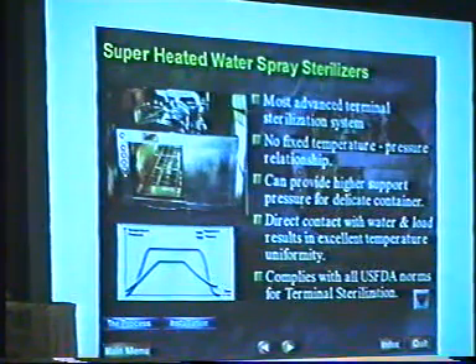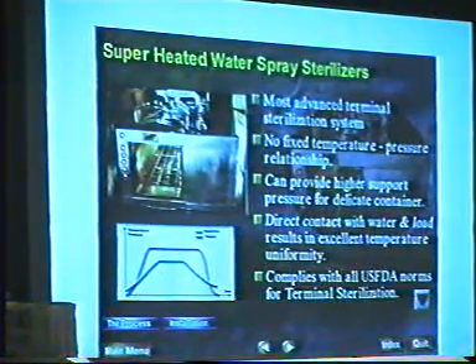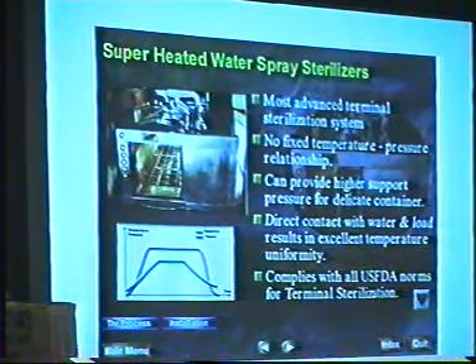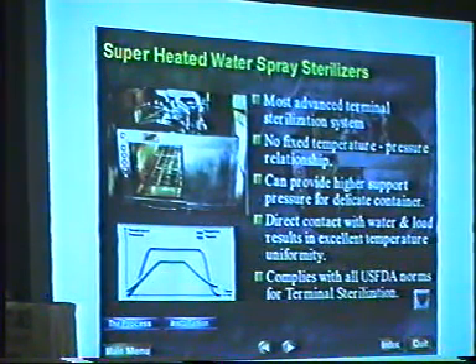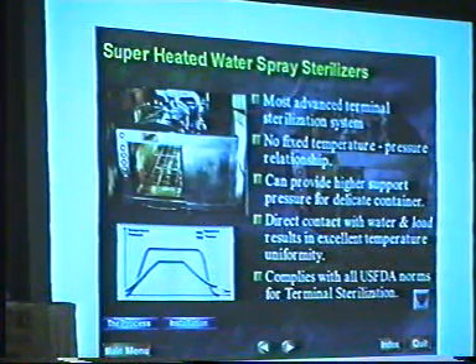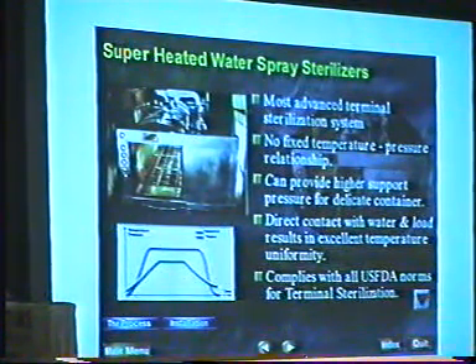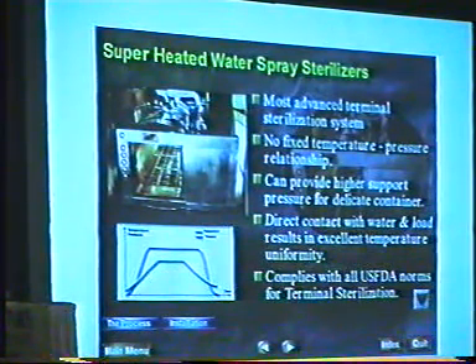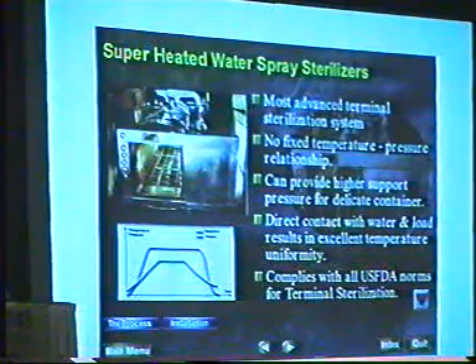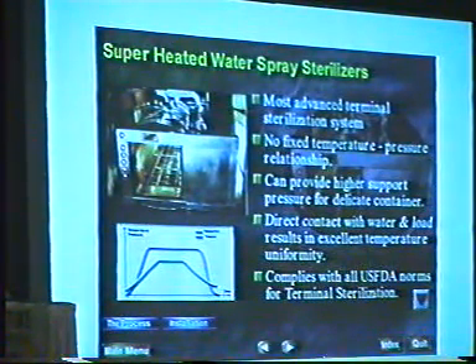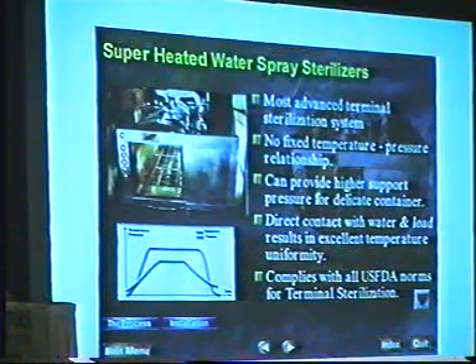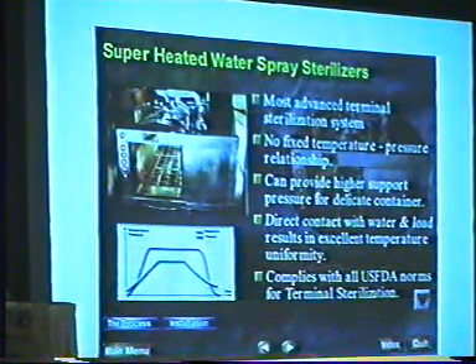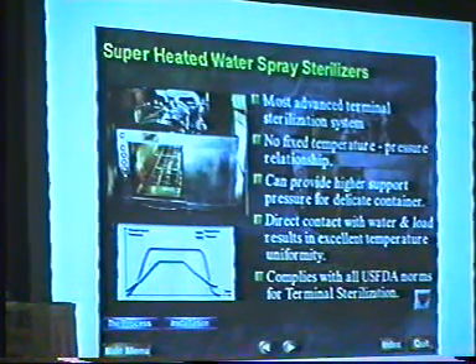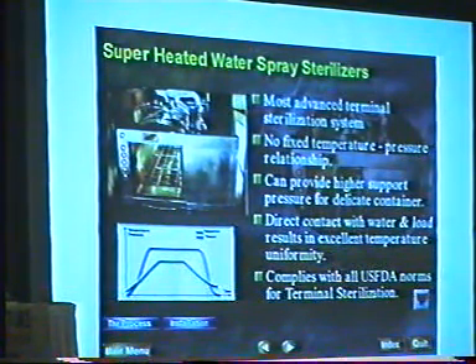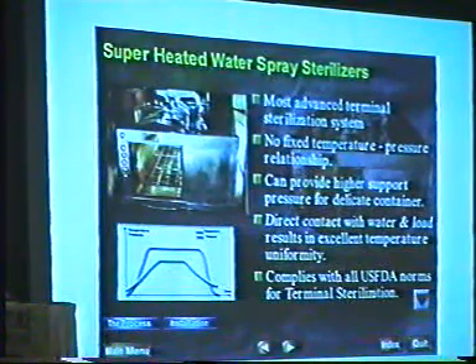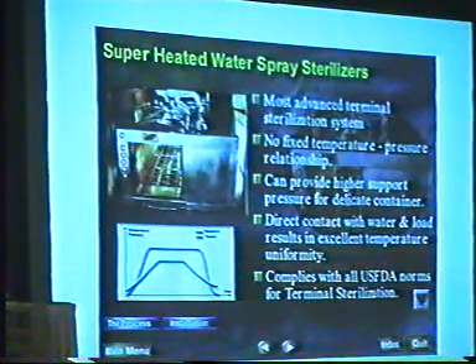Number two is, since the heating medium is now liquid, the water remains in the liquid form even at 108, 110, 115, 120 or 125, whatever is your temperature. Water is deliberately kept in the liquid condition by increasing the system pressure so that you are heating by liquid medium. So presence of air ceases to have any meaning so far as your process is concerned. So our old problem of cold spot, air being present, air removal efficiency, all these issues are simply not relevant for these two machines. And because the heating medium is liquid and it is moving with a high velocity, heat transfers are better, temperature uniformities are far better than you can ever achieve in a conventional process.